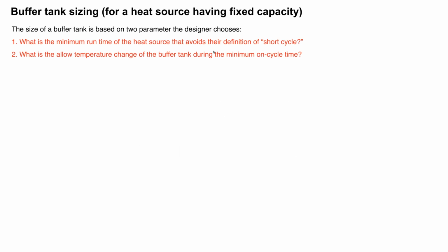So let's talk about buffer tanks, okay? The idea of a buffer tank: anytime you have a heat source that has a fixed heat output capacity, and the Enertech unit does have variable capacity, but let's divert from a heat pump. Let's say we're talking about a boiler. It really doesn't matter what that heat source is. It's a box that produces heat at so many BTUs per hour, and we're coupling that to a distribution system that might be highly zoned. We might have each room in a building as a separate zone, or we may have some small rooms that have small emitters that only need maybe 1,500, 2,000 BTUs per hour.